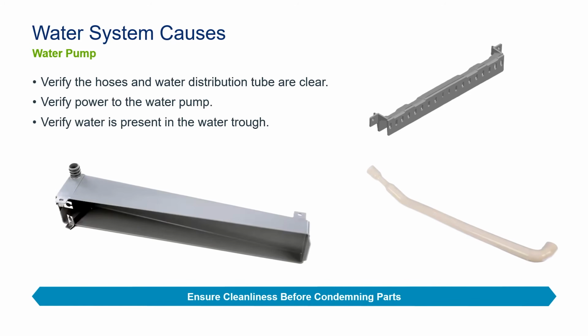So with the water pump, I've already kind of covered this, but let's be sure that everything is clean. Up there at the top right, you've got the distribution tube. If it's all caked up with calcium and water cannot cascade over the evaporator properly, that's going to lead to a service limit 1. What's going on with the water trough? Can we move water properly? The distribution hose there at the bottom right, is that all impacted? Ensure cleanliness is taken care of before you ever condemn any parts.